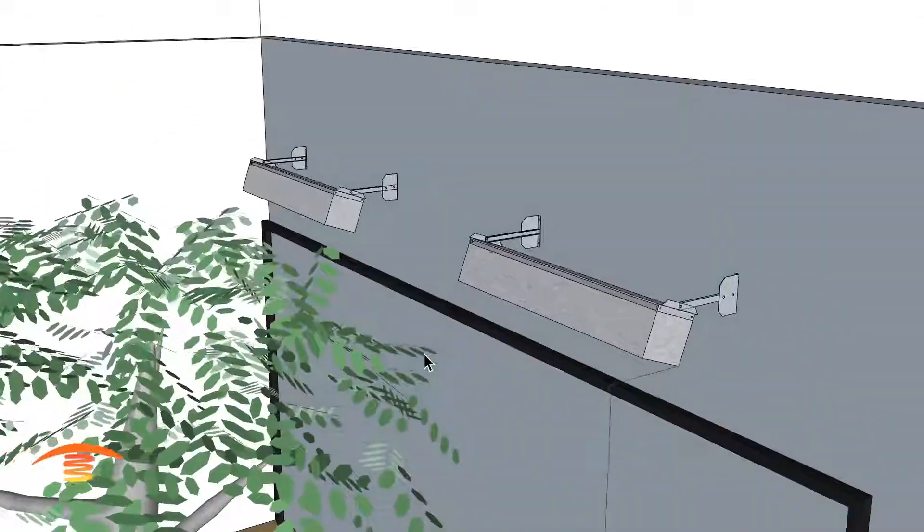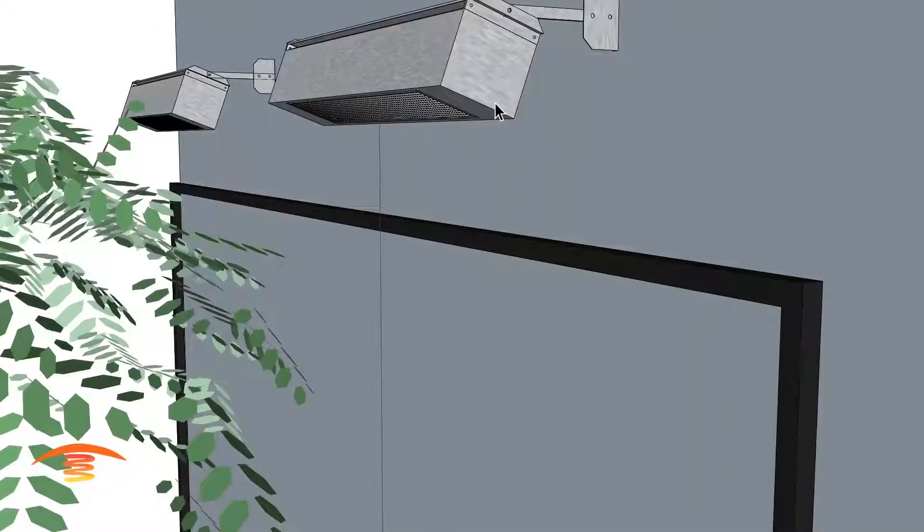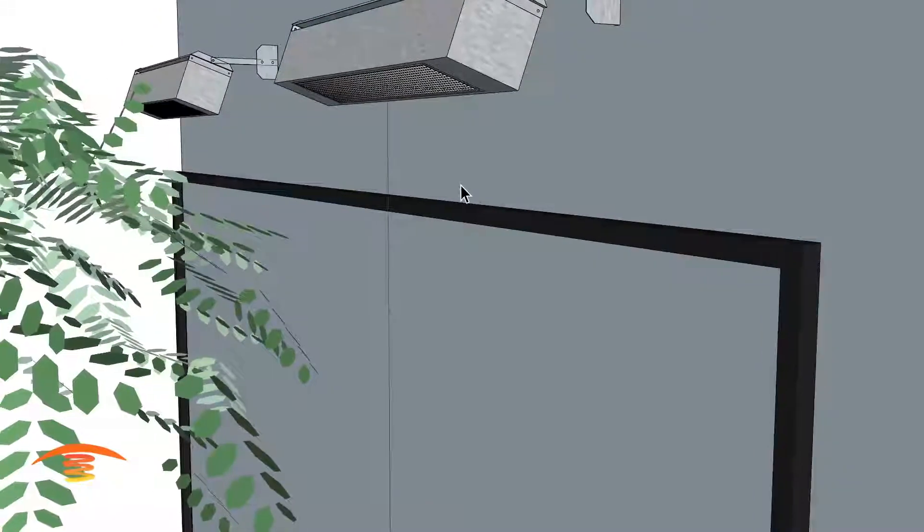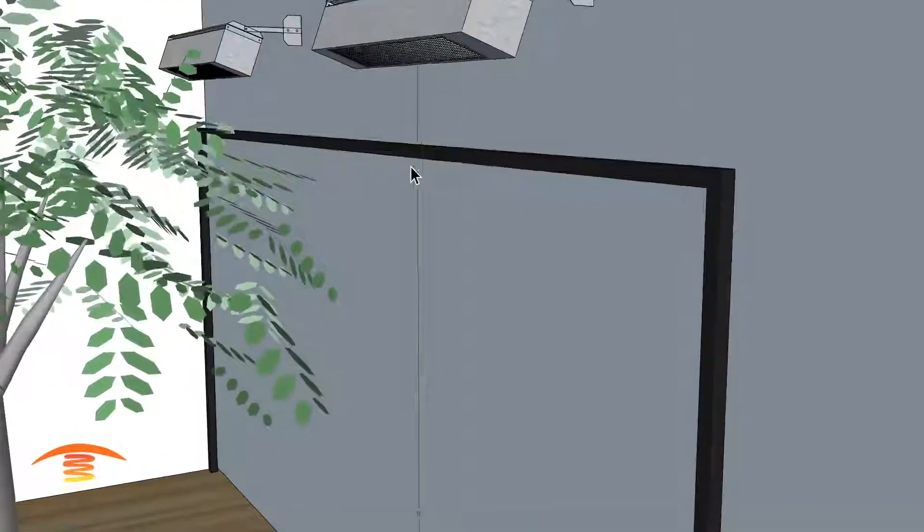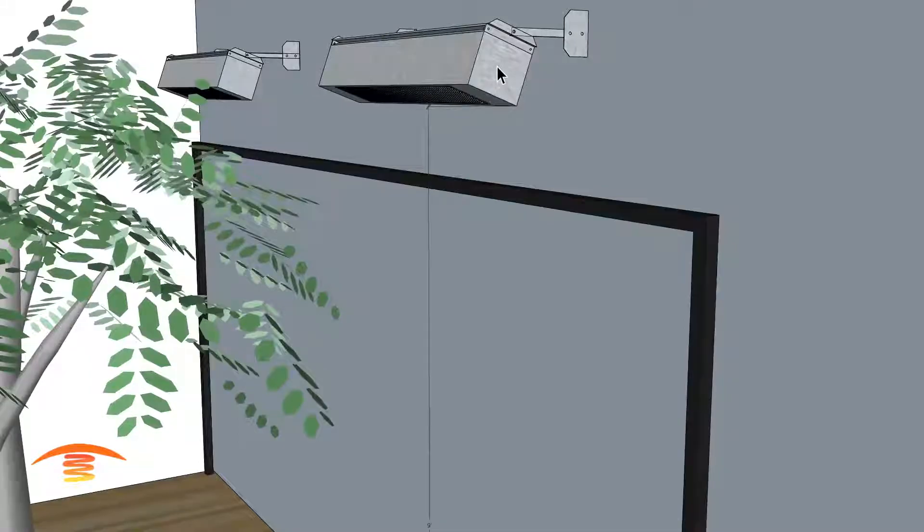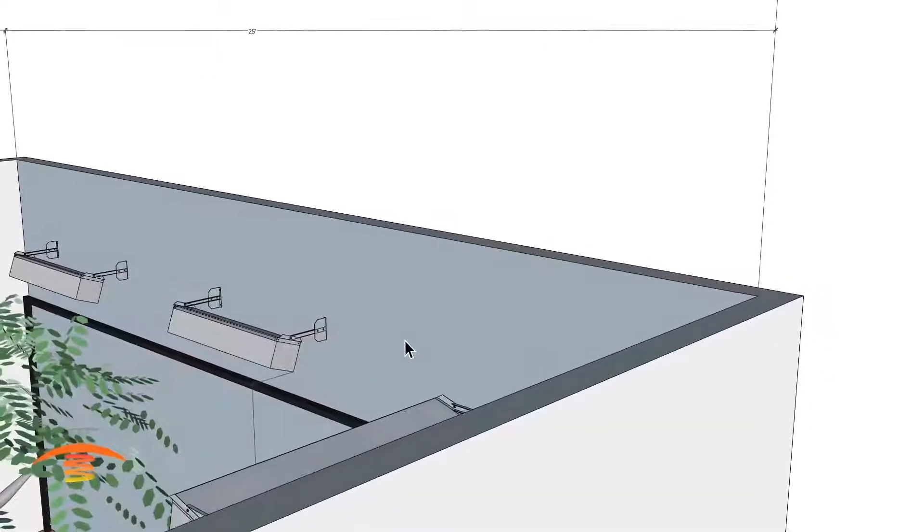Also, just a side note, we moved this particular heater about two feet higher than what they had the other heaters before. So this heater is about nine feet off the ground, which nine to 10 foot would be ideal. You could move this 10 foot and that would be great as well.